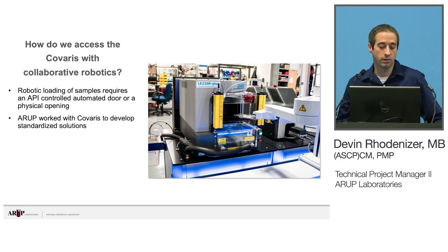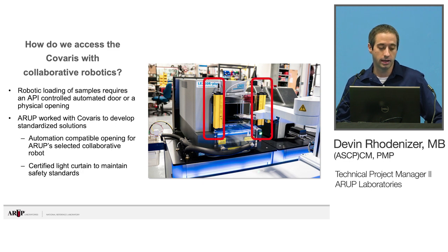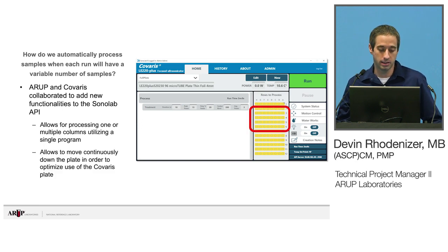We worked with collaborative robots, and it really requires either some sort of API-controlled automatic door or a physical opening. We worked with Covaris to develop a standardized solution for the LE220R Plus, adding a compatible opening for our precise arm that actually works for most collaborative robotics out there. By adding that opening, we also created a potential safety hazard, so a certified light curtain was added to maintain security — if someone tries to stick their hand in there, it will shut off. We also collaborated on changes to the Sonolab API so that we can utilize one program to process either one column or multiple columns without having to call a separate program depending on the number of columns. This also solved our problem of optimizing plate use — we can just move down the plate without changing plates.